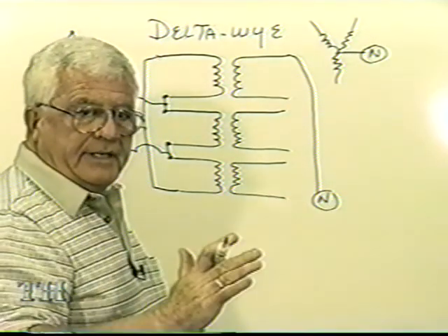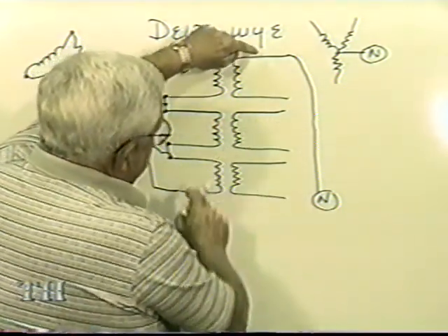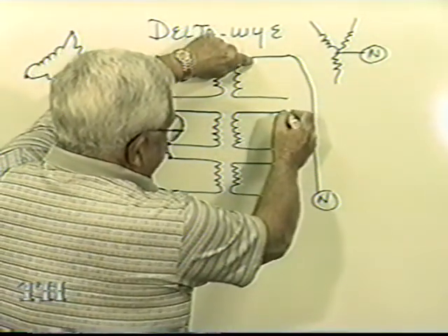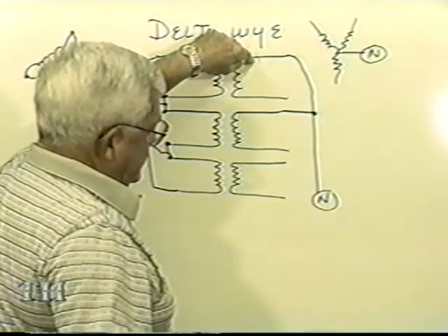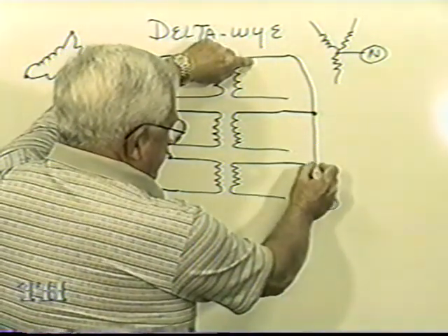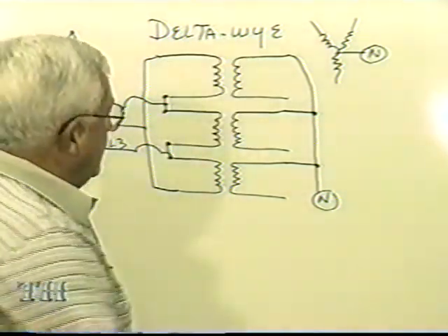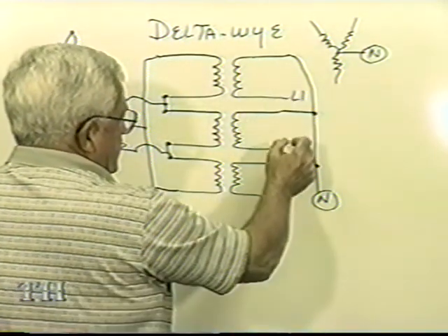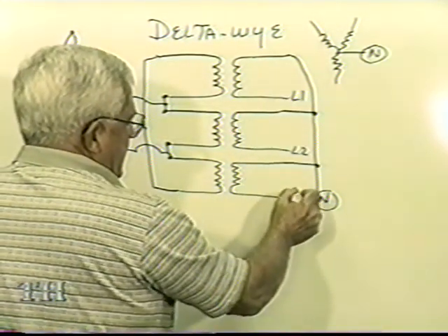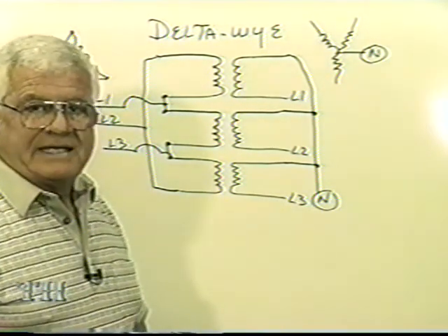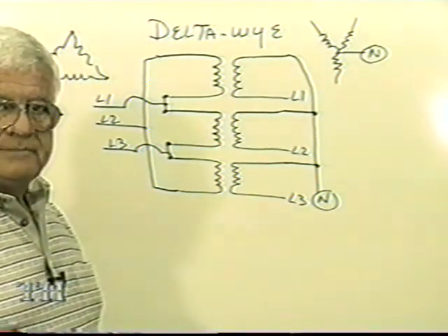Now for polarity purposes, since I come off the top of this winding, I'm going to come right off the top of this winding and make my connection, and right off the top of this one and make my connection. All I have to do is go line 1, line 2, line 3. There's my connection for a delta Y.